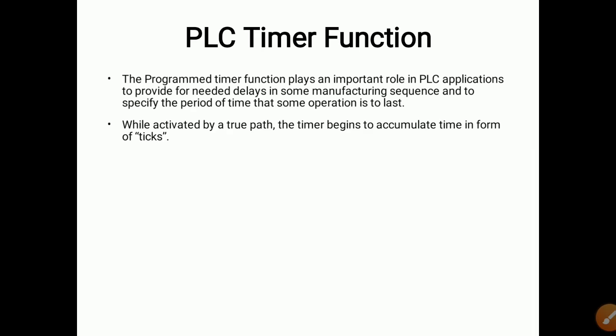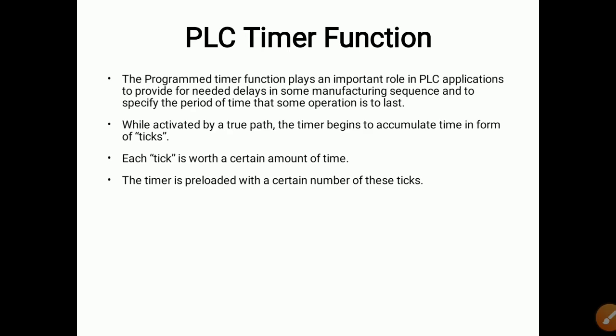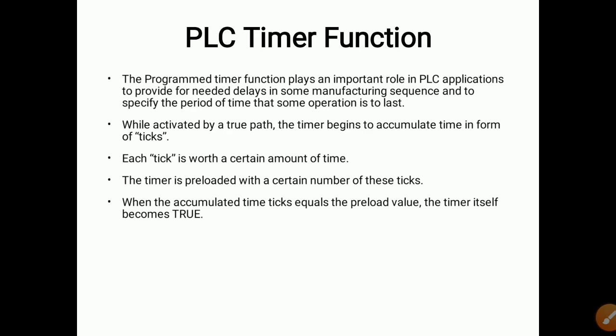While activated by a true path, the timer begins to accumulate time in the form of ticks. The timer has a clock-type device, so it accumulates time — one tick, two ticks, three ticks — and each tick is worth a certain amount of time. The timer is preloaded with a certain number of these ticks, meaning we give some preset value and according to that the timer is preloaded.